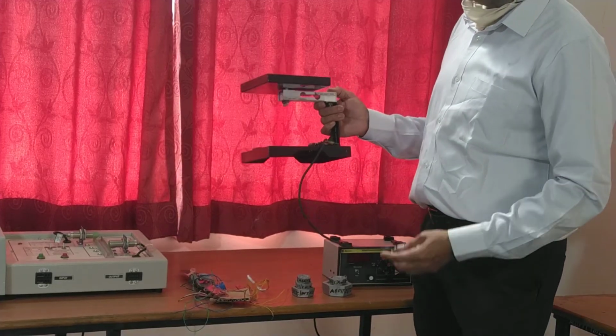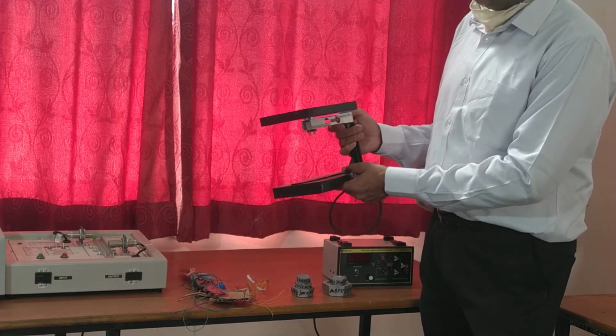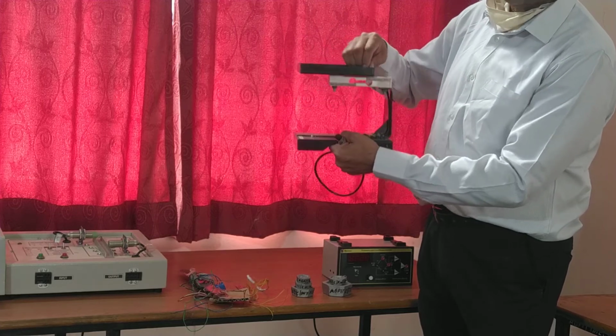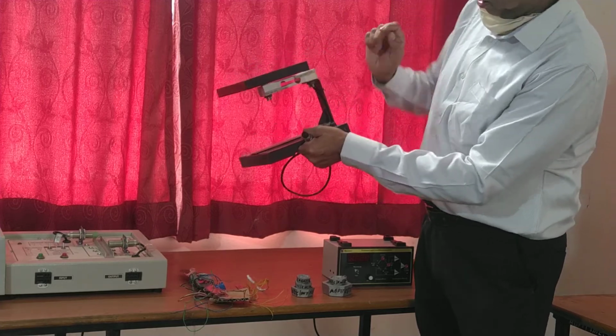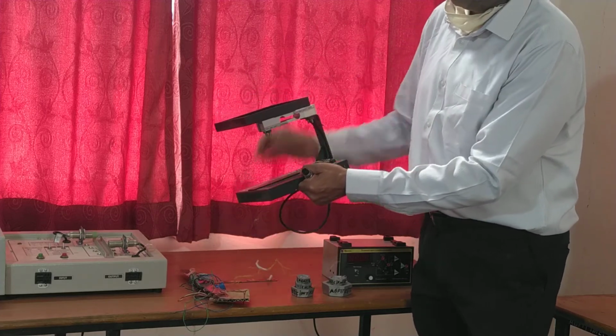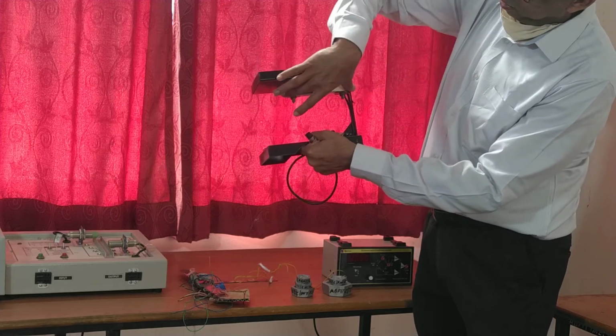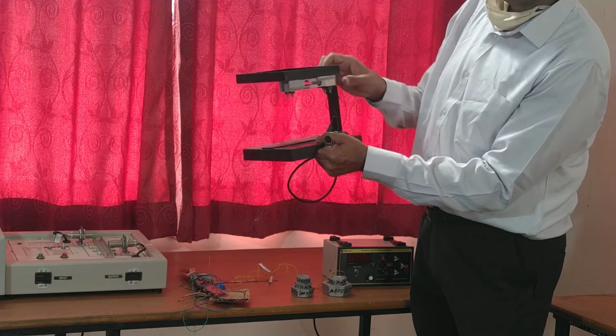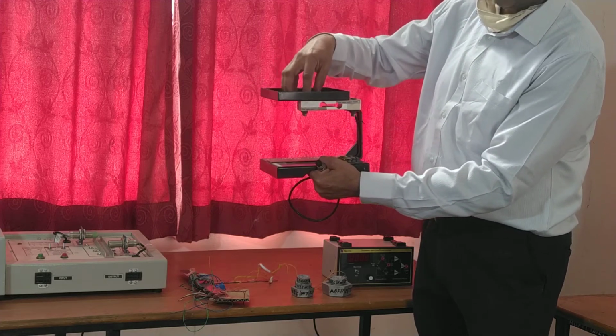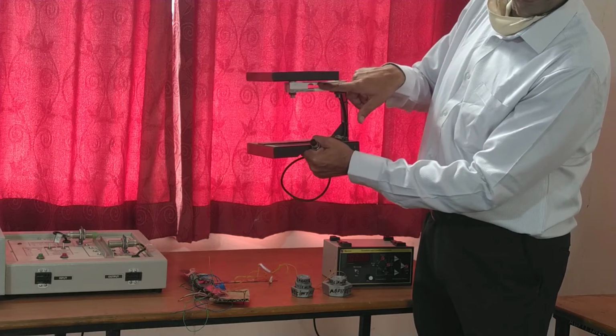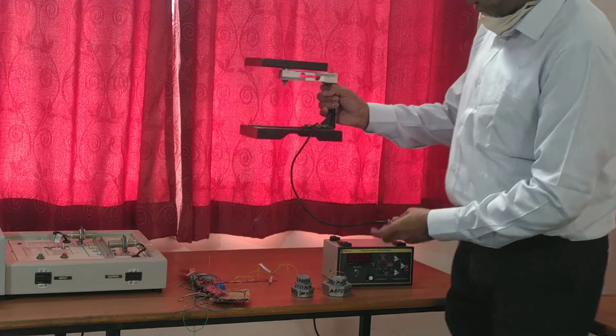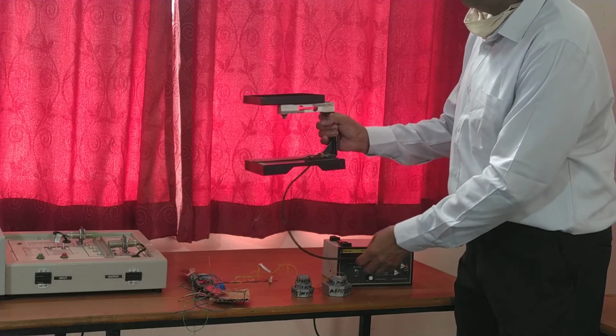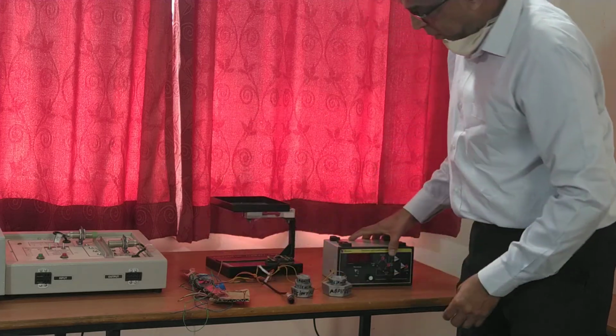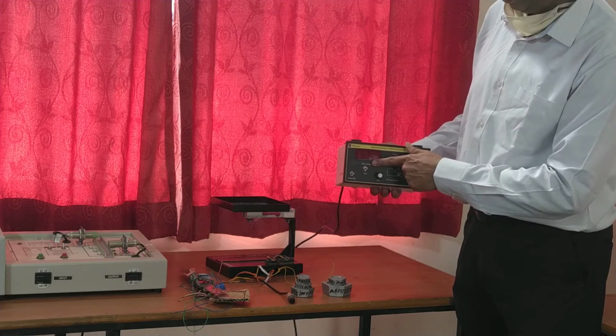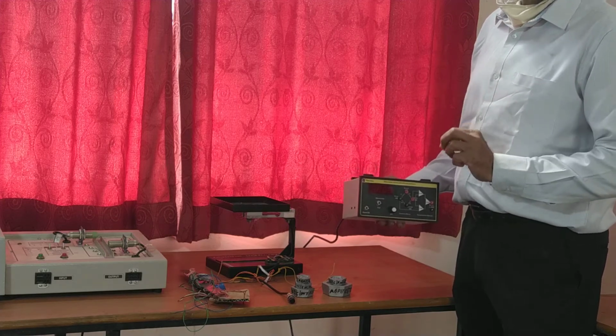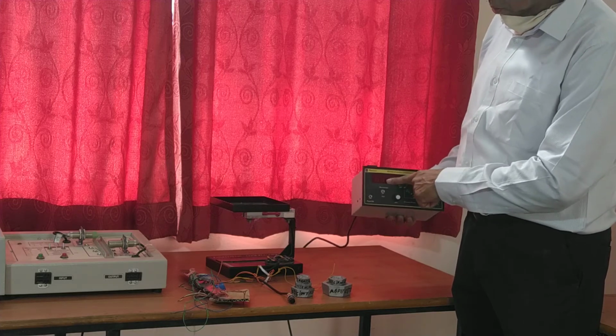So I was talking about the commercially available strain gauge load cell, right? For applying load force, as you can see here, there is a pan, and this is the cantilever beam, similar to the beam we just saw. This is a cantilever beam of rectangular cross section, and I know the length, right? I know the cross sectional details, thickness and width, and I can apply the force or weight. I have the strain gauges mounted on this beam, and those are connected to my signal conditioning circuit here. So corresponding to the applied loads, I will be able to measure the micro strain directly, or this can be used as a load transducer or force transducer. So it can show me the force directly.